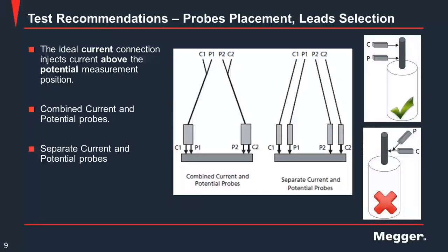As you can see at the right side of the screen, this is the checklist, the green checklist indication. You can see here the current probe with the letter C and the potential probe with the letter P must be connected like this. So the current probe is above the potential probe, because you don't want to measure the voltage that is affected by the current injection.